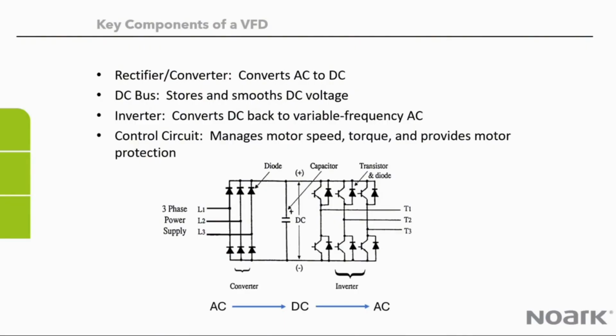So this is an electrical diagram of what a VFD actually looks like inside. Up here we talk about the rectifier. AC power comes into these three terminals, this section right here, and you can all see my mouse, correct? That section is actually going to be a diode bridge. On bigger drives, they might be SCRs. We basically rectify the voltage to make the DC bus voltage, which has our capacitors. This symbolizes the capacitor section. It could be multiple, and probably has multiple capacitors.